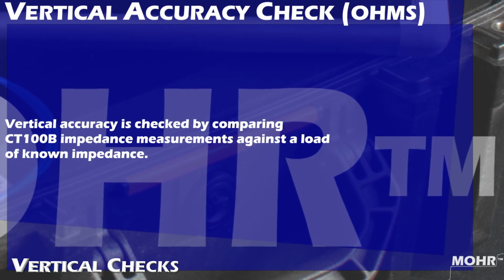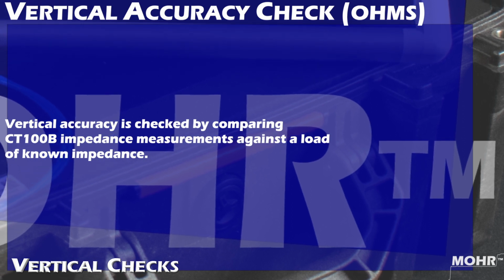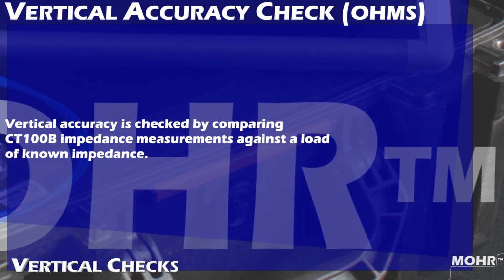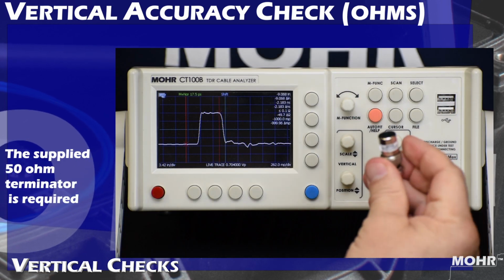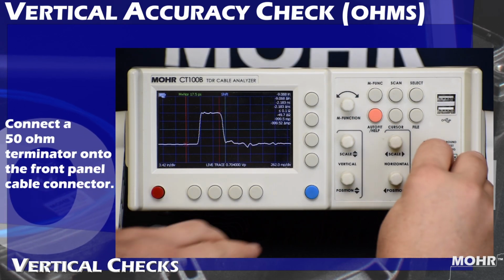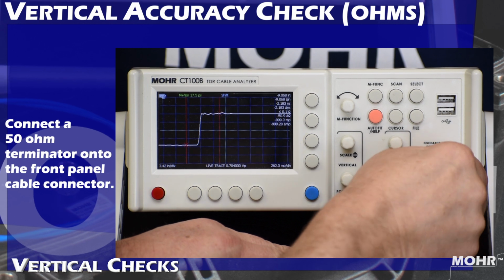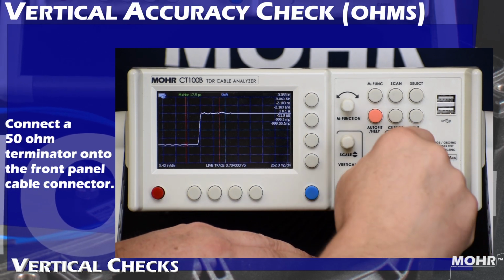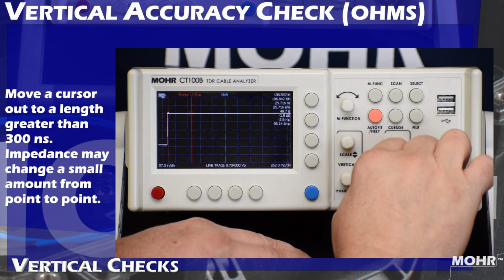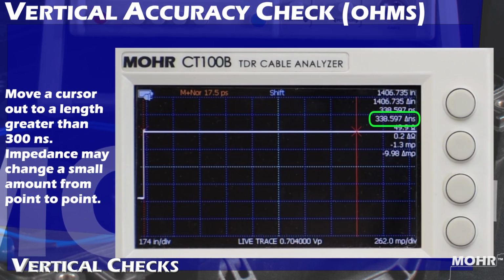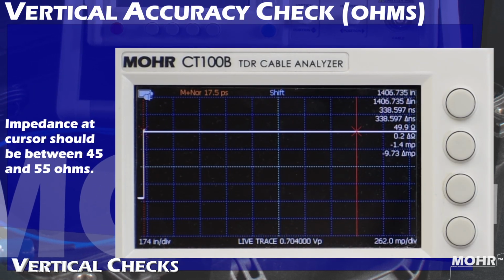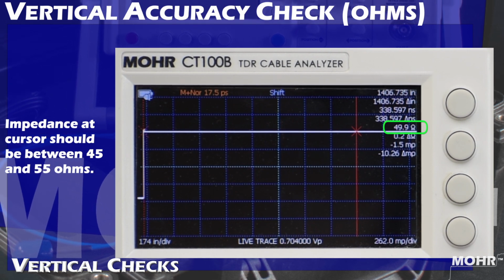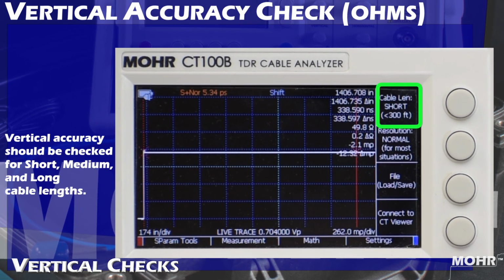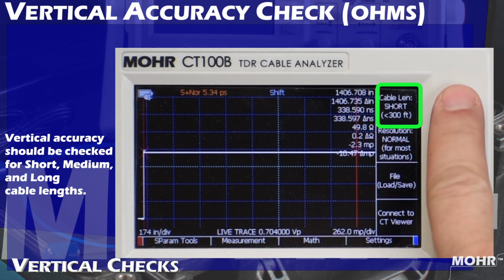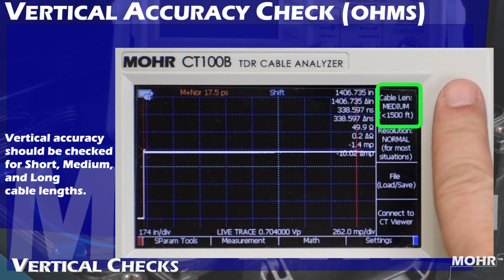For vertical accuracy check, vertical accuracy is checked by comparing the CT100B's impedance measurements against a load of known impedance. The supplied 50-ohm terminator is required for this. Connect the 50-ohm terminator to the front panel connector, and move the cursor out to a length greater than 300 nanoseconds. Impedance of the cursor should be between 45 and 55 ohms. Vertical accuracy should be checked for short, medium, and long cable lengths.